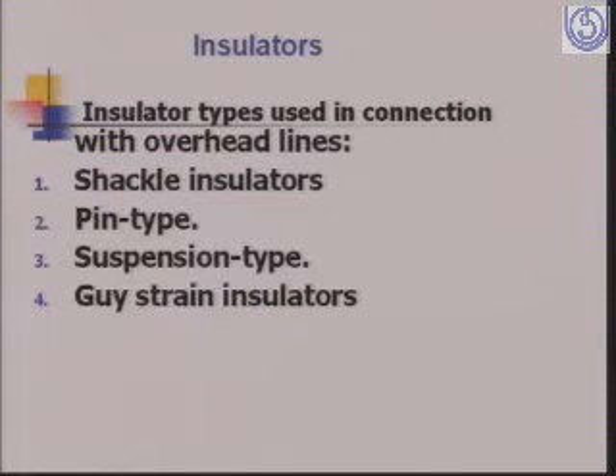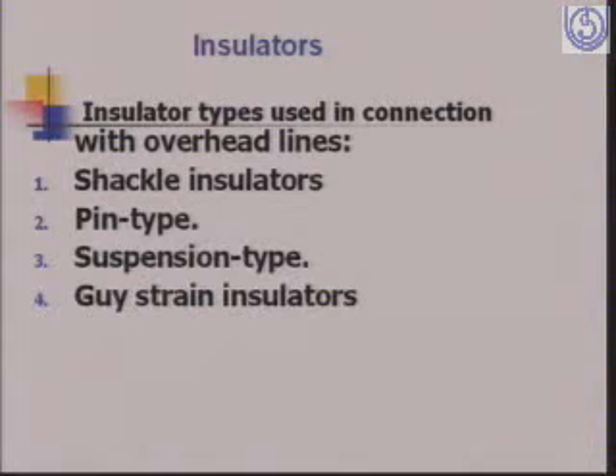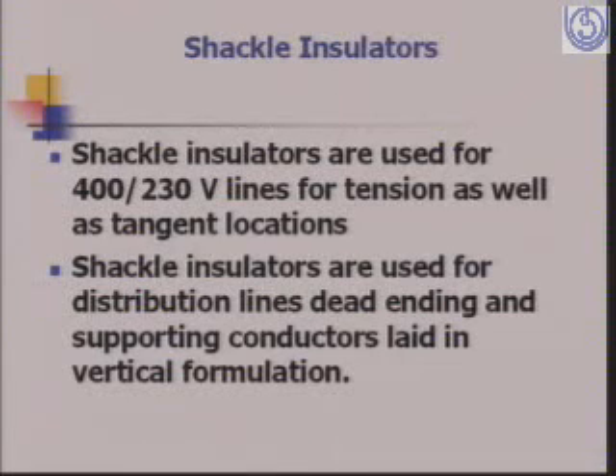The various types of insulators which are used in connection with overhead lines are the shackle insulators, the pin type insulators, the suspension type insulators, and the guy strain insulators. We will go into each of these insulators. The shackle insulators are used for 400 and 230 volt lines for tension as well as tangent locations. Shackle insulators are used for distribution lines, dead ending and supporting conductors laid in vertical formation.